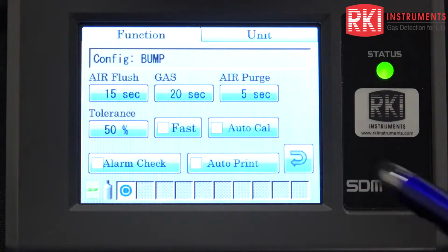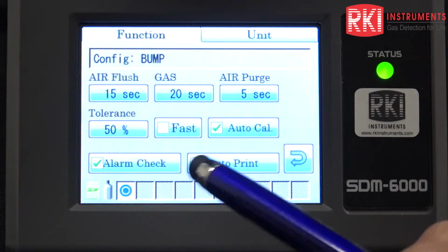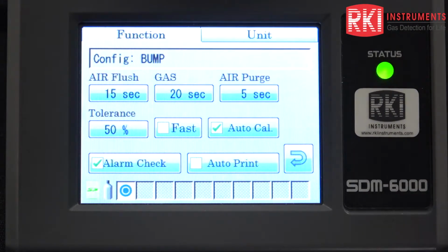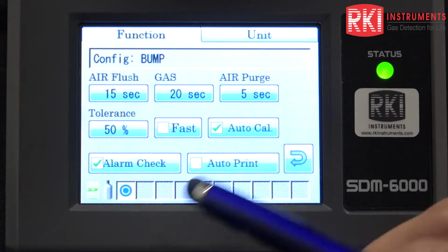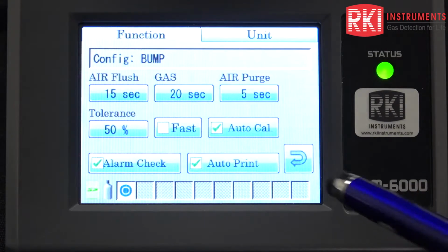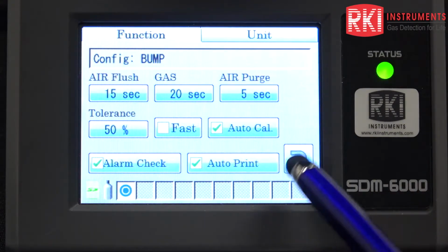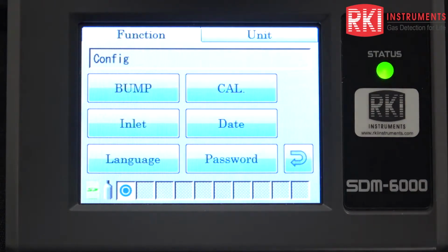AutoCal: if it fails the bump and you have this checked, it's going to automatically perform an auto calibration. Alarm check: if you have it checked, it's going to automatically perform an alarm check right afterwards. And the same with auto print: if you have a printer connected, it's going to print out the data.